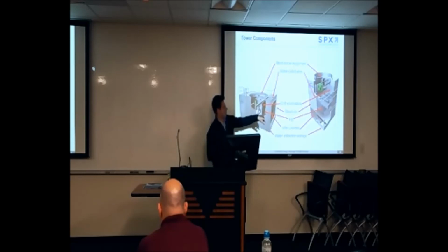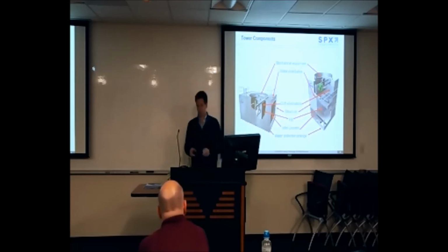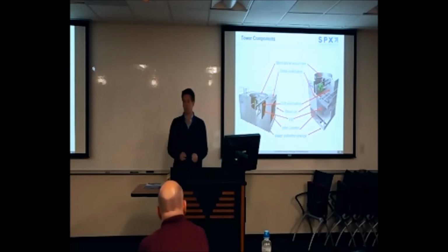With the counterflow, all the components are stacked on top of each other, so it's much more difficult to find points of entry to do maintenance. So you'll spend a lot of your time inside that maintenance access area, which brings me to a good point. Before we can talk about maintenance, what do we have to talk about? Safety, right? The most important thing with safety when it comes to cooling towers is to make sure that you lock out, tag out before you do any work inside the cooling towers.